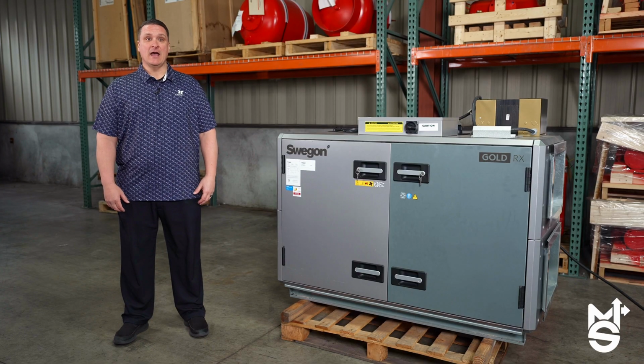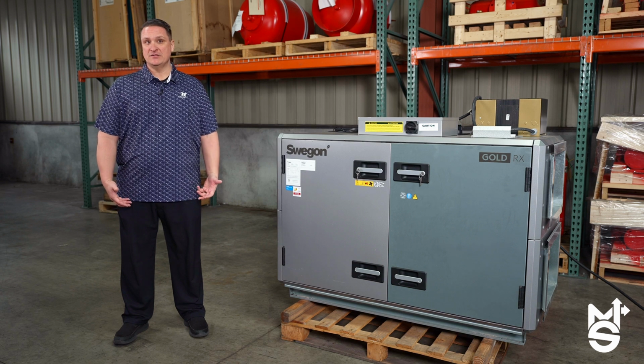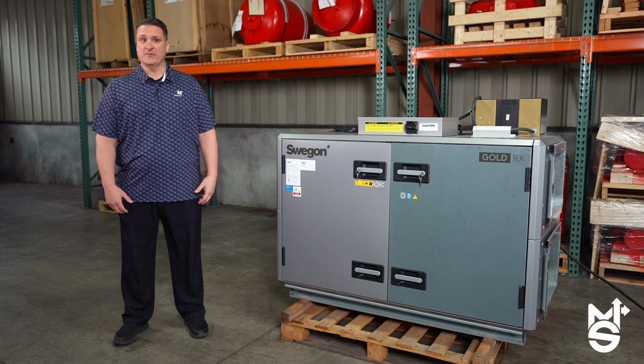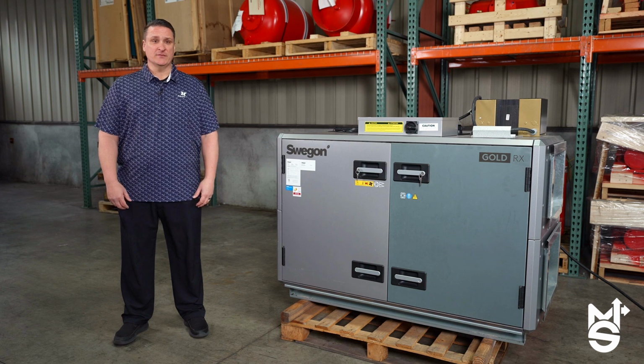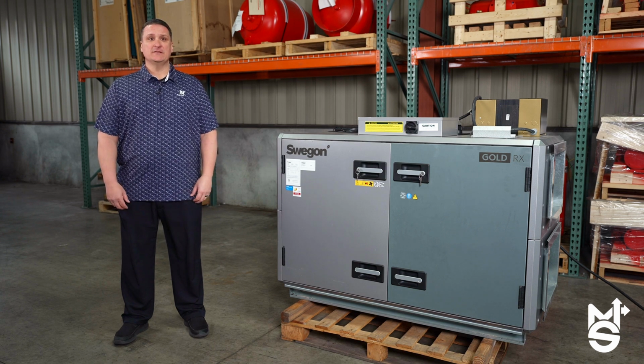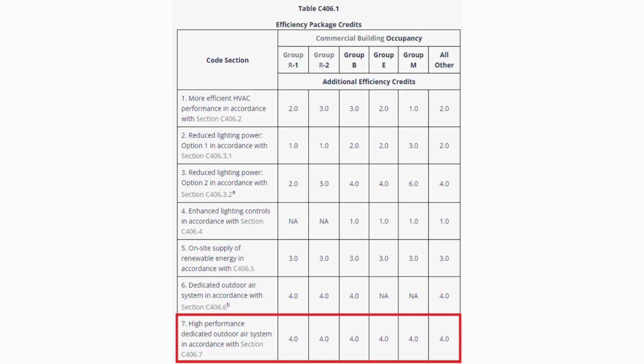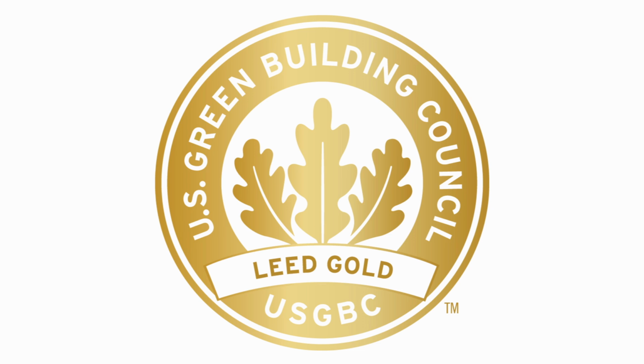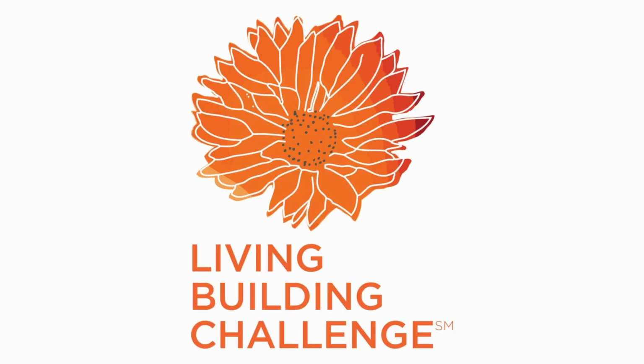Codes at the city and state level have various performance requirements associated with the efficiency of the building HVAC system. Swegon's capabilities of delivering high-performance units in the form of meeting a fan energy usage of, say, 0.5 watts per CFM, for example, or sensible recovery effectiveness of over 80%, allows us to meet codes like C406.7 of the Washington State Energy Code or local City of Seattle codes. Many government entities are beginning to enforce building performance standards or have sustainability goals that include LEED Gold, Net Zero, or Living Building Challenge, all included capabilities of the Swegon Gold RX DOAS units.